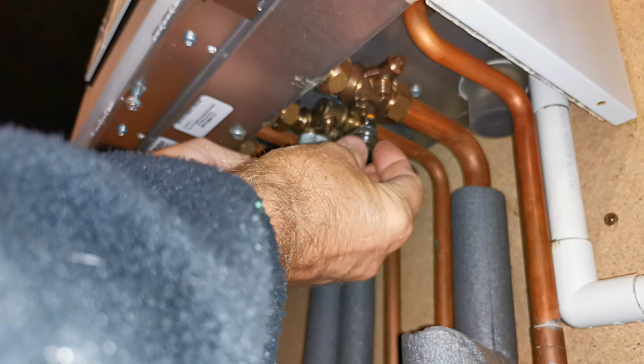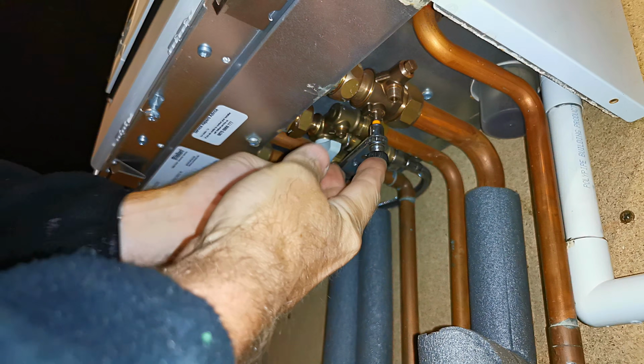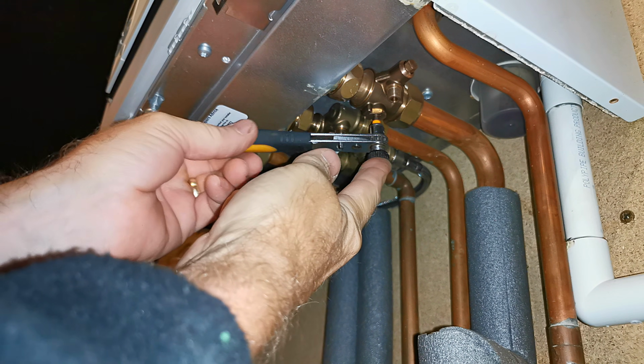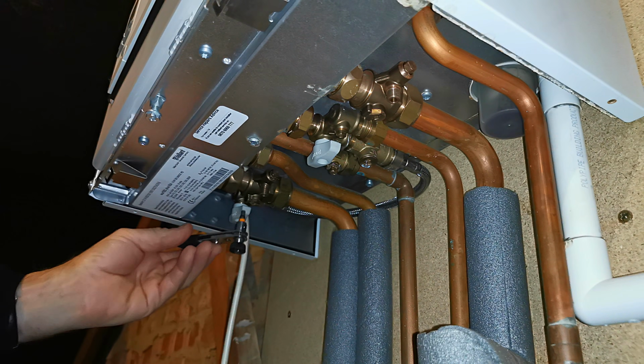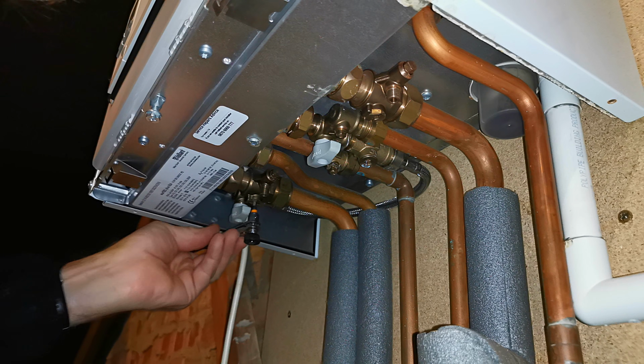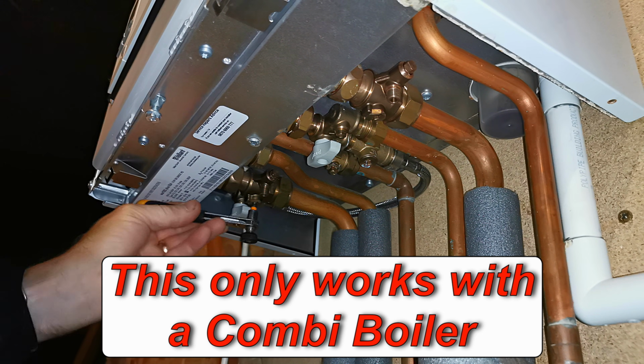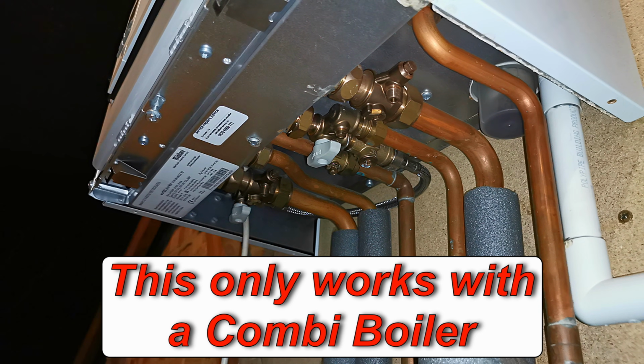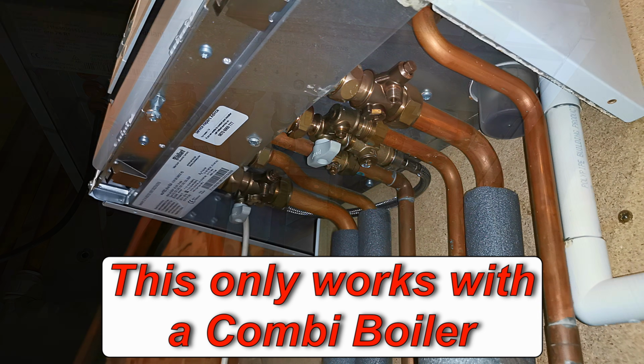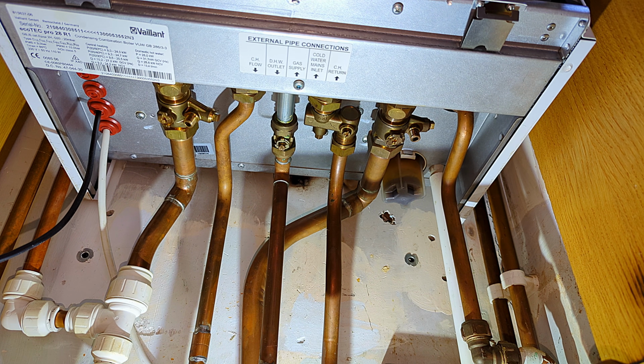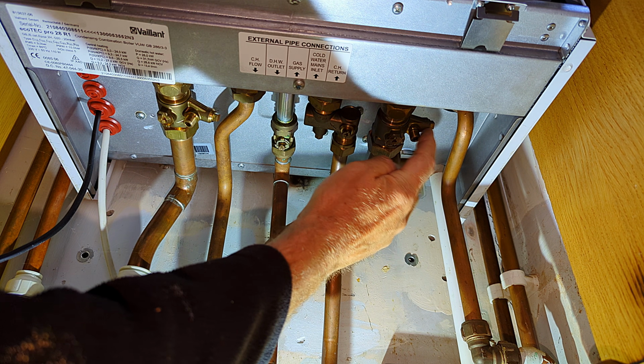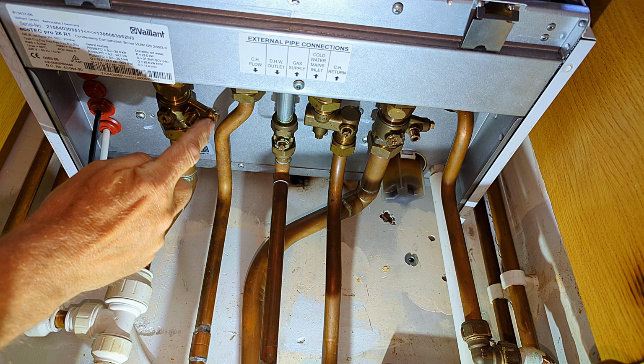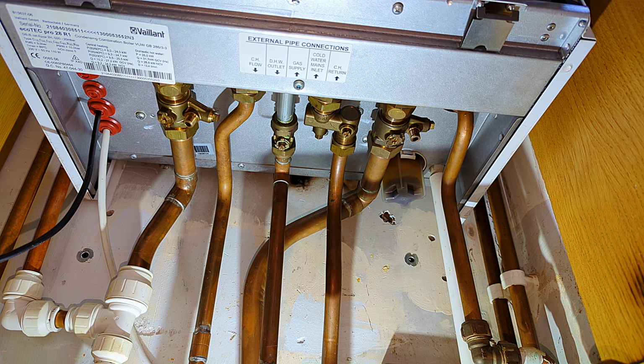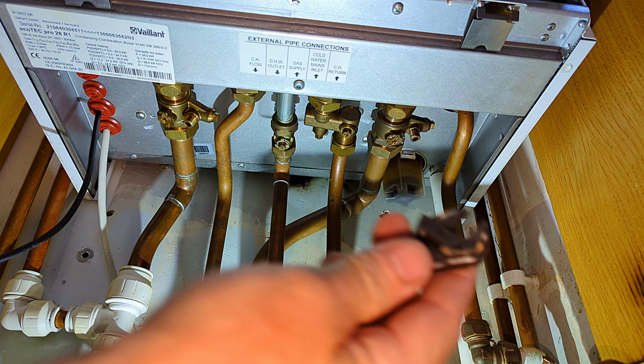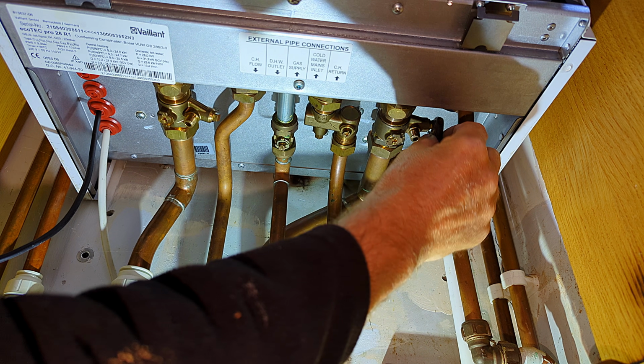I don't always isolate the boiler. If I think the valves look at all dodgy, like they've been leaking, and I don't really want to turn them, then all I do is to put the boiler into hot water mode. So I run the hot water tap, then turn the boiler off. That will create an airlock on the central heating system, so I should then be able to change the pressure sensor without lots of water pouring out, but I'll still need to drop the pressure on the system, and I'll need to drain more water out because I haven't isolated the boiler from the rest of the central heating system. Now, I just showed you the two drain points which are on the Vaillant boilers.